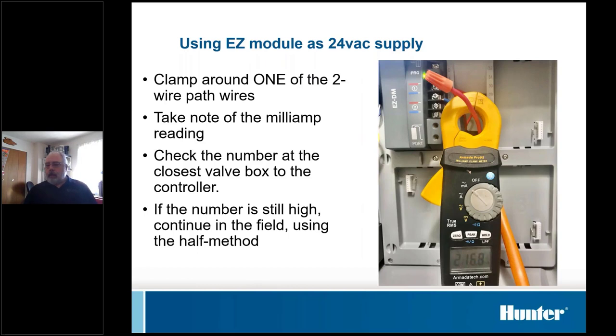Hey, Dave. Yeah. I just want to stress to everybody on the line, I'm not sure what everybody's comfort or skill level is with troubleshooting two-wire irrigation, and coming from someone who spent years doing the half method, using a solenoid and a clamp-on amp meter will take you from a novice to a pro in 10 seconds. So if there's anything critical you take from this, it's how to use the clamp-on amp meter to find it and to troubleshoot without taking all of those connections apart.